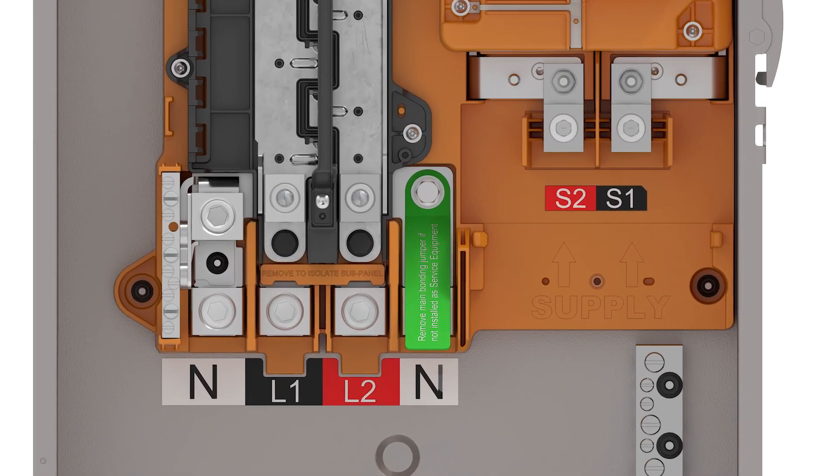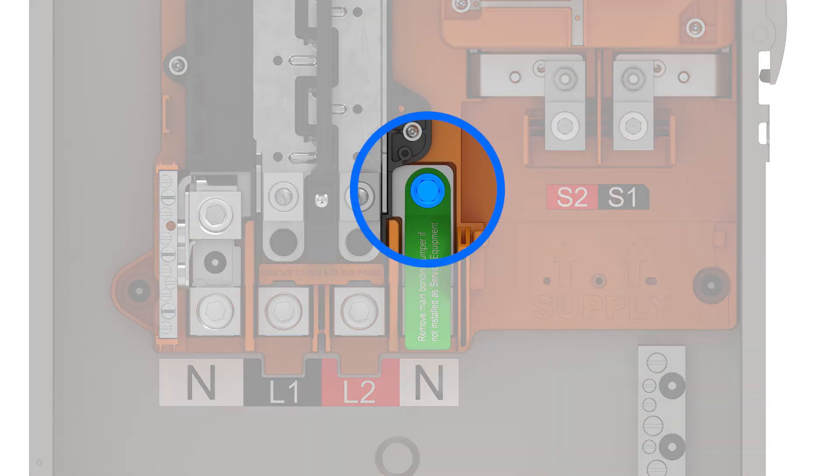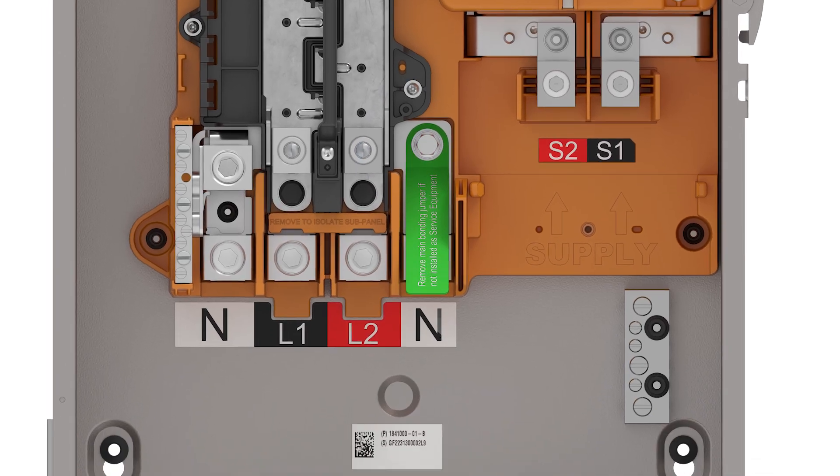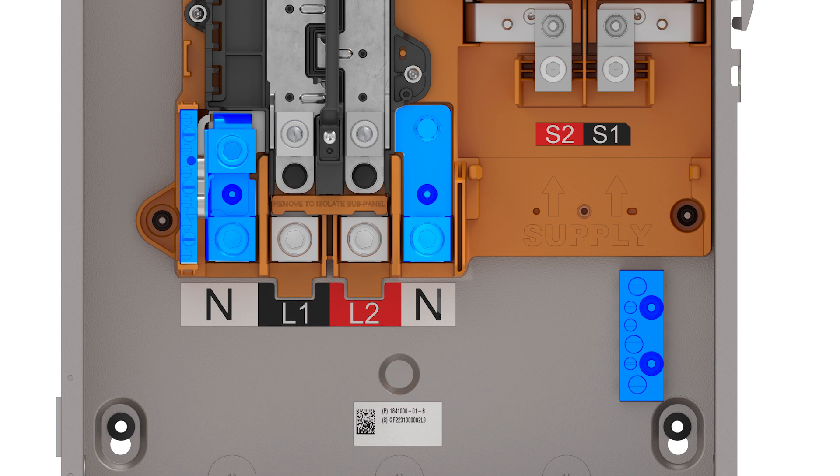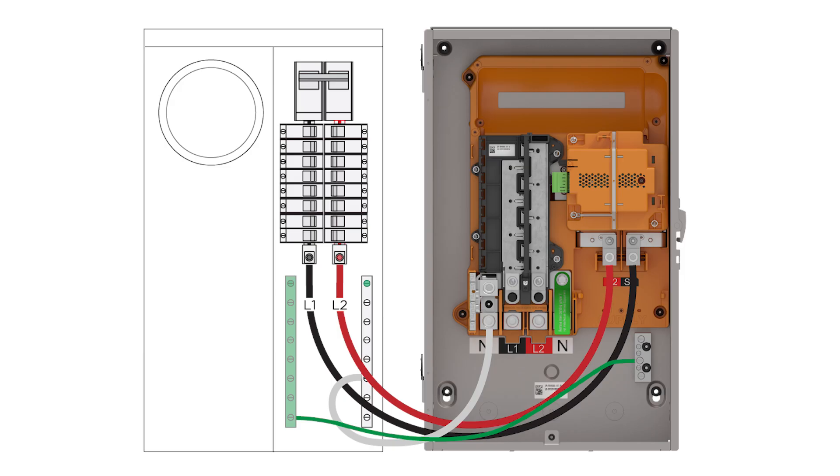Gateway comes with this bonding screw pre-installed, creating an electrical bond between the neutral bussing and the ground lugs. Neutral and ground must only be bonded in the first means of disconnecting power to the home's electrical system. When Gateway is fed from a service disconnect, this bonding screw inside of Gateway must be removed.